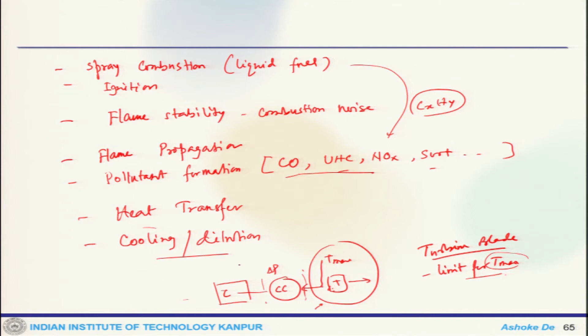Now, some problems in GT applications. Some of them are still existing problems, some are quite well handled. For example, if you look at NOx control, this is still a problem, one has to actively look at it, and the GT industry does look at it, but obviously NOx is not decoupled from another issue, which is CO or UHC, because the behavior of CO and UHC is slightly different compared to NOx, and that is why some level of trade-off is required. NOx, if it is not fuel-bound, is primarily formed because of the temperature in the post-flame region, where thermal NOx formation is quite active, and that is what dominates. But at the same time, if your temperature is high, CO gets completely oxidized, so that helps.